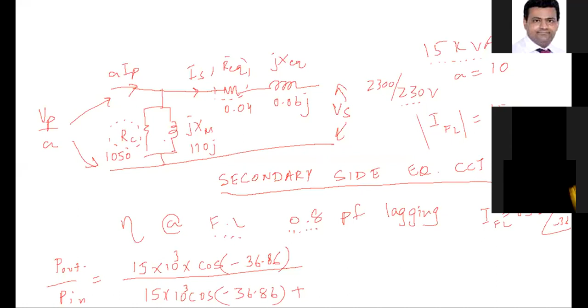So efficiency is always whatever output you are extracting from your machine versus what input power you are giving to your machine. The output power in this case is equal to the rating of the transformer, which is 15 kVA. You want to give your load 15 kVA, but there is always some power factor associated that relates this apparent power into the real power. So in this formula for efficiency, you always use the real power, and the formula for real power is apparent power times cos theta. We have already done this in the ENA course.